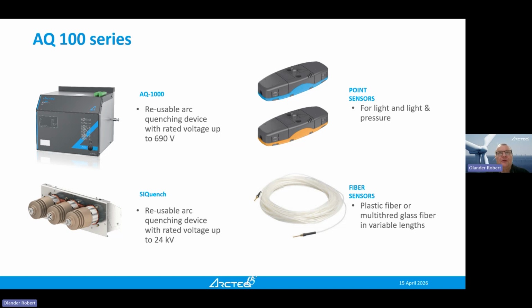It will move the energy from the arc fault to the inside of the quenching device, and then it's designed so that it can take 100 kiloamperes for 200 milliseconds. So it means that it can take the fault current inside itself until the breaker opens. So it's actually quite a robust device. And we are the only one on the market with a device which you can do mechanical operations. You can test this device.